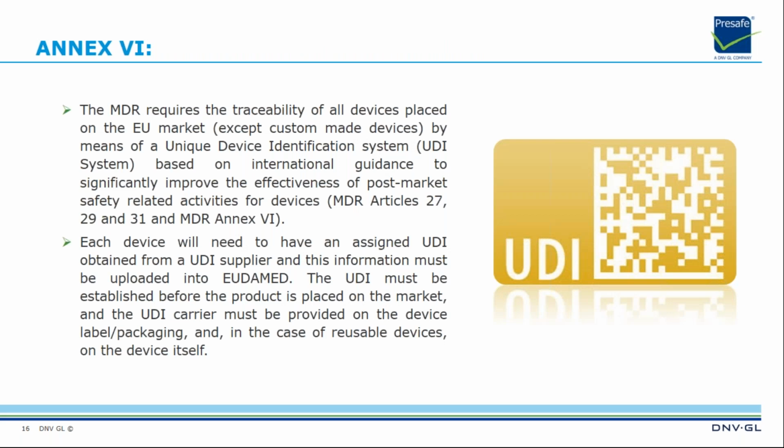Annex 6 is about those requirements, identification by the manufacturer. Actually, it's about the UDI system, unique device identification, and the MDR requires the traceability of all devices placed on the EU market, except custom-made devices, by means of a unique device identification system, UDI system, based on international guidance to significantly improve the effectiveness of post-market safety-related activities for devices.